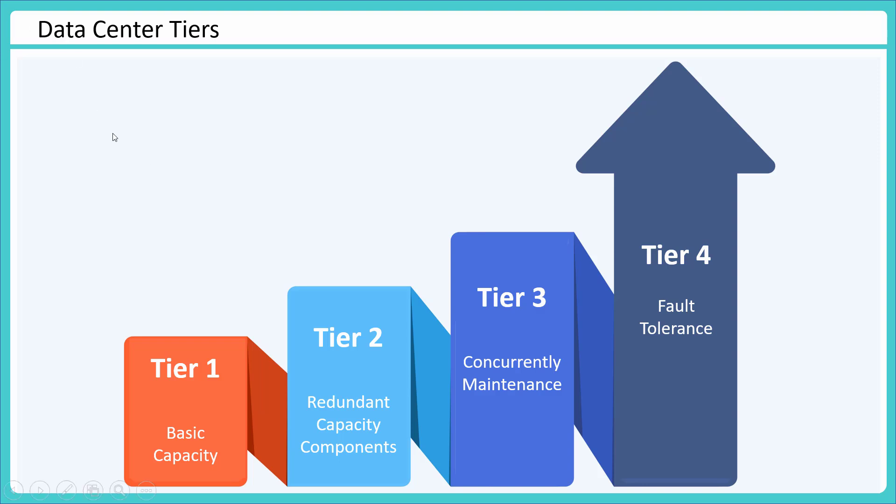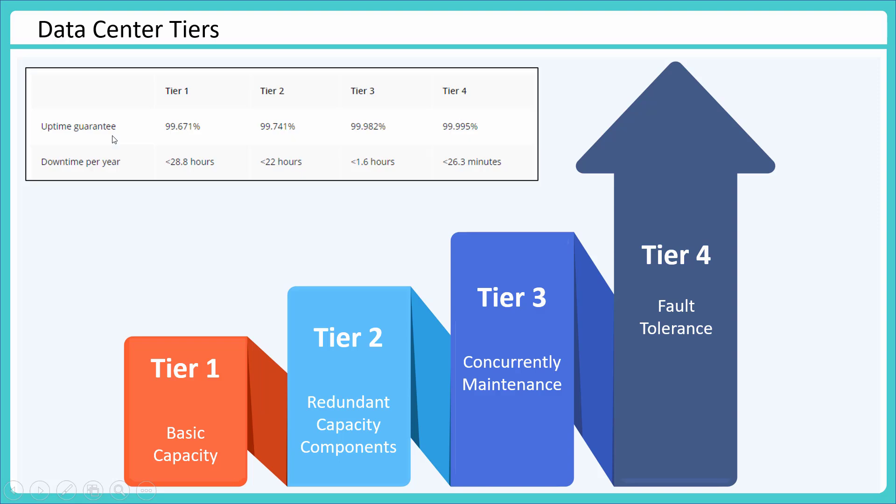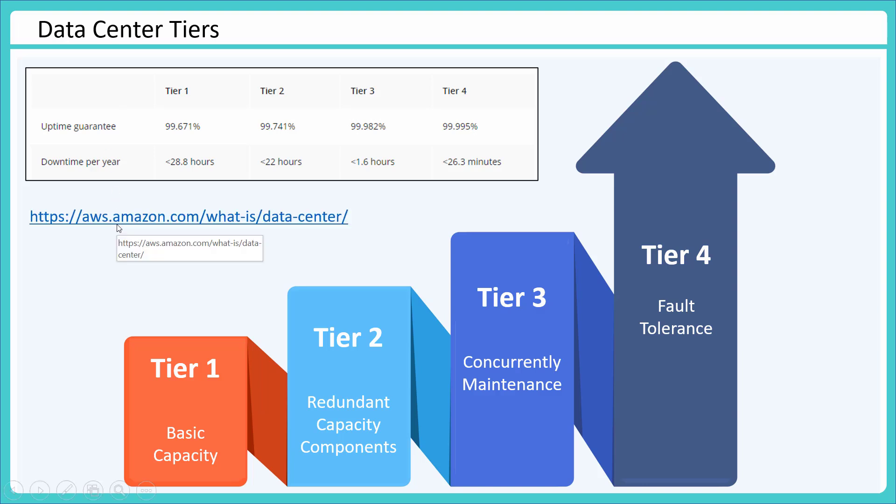Now how do we manage or measure all this information? So we talk about uptime guarantee when it comes to data centers. When you are going into a data center for hosting your application, probably you would ask or read their documentation about what uptime guarantee they are giving to you. Is it 99.671%? Then it will be a tier one data center. If it is a tier four, they would be giving you 99.995% of uptime guarantee. Again, it does not mean it will never fail, but they have mechanisms in place to ensure that even if one of the components of the data center fails, they have redundancy, they have fault tolerance so that they can keep your applications and services running. So this is how data centers are bifurcated. You can get more information on this particular link. I will keep this link within the resources section so you could look into it.